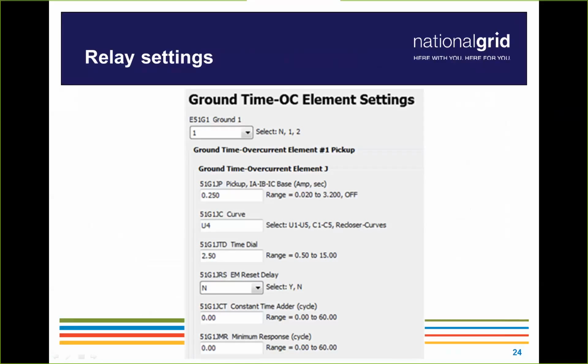We would require, if you had a relay, that you submit that relay's data file in its native format. We have the ability to open a variety of different relay data files, and we would look at the data file in its native language and make sure that the settings that we agreed upon are the settings that are being developed to be installed into the relay. So now that's with a regular relay that you would program that would be external to an inverter, something such as a recloser or a relay for a medium voltage breaker or something of that nature.